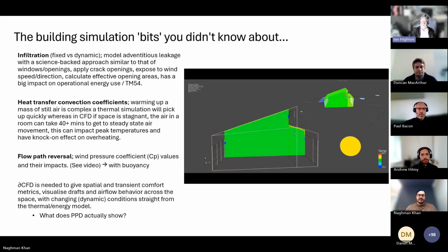Thanks to Hilson Moran for that, by the way, because they did a full external CFD flow calculation, compared it to what we were doing, and the differences weren't huge. So that's great news from a dynamic simulation point of view. It doesn't mean you've got to spend a lot of time and effort and money doing external CFD to get pretty decent results. So yeah, very positive.